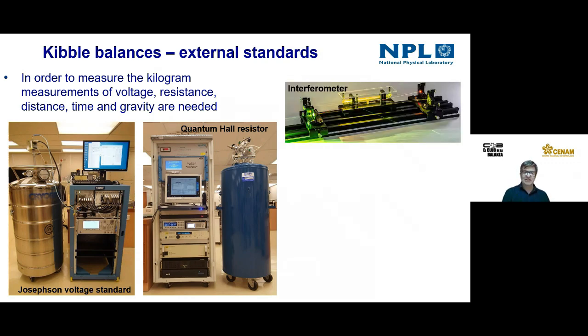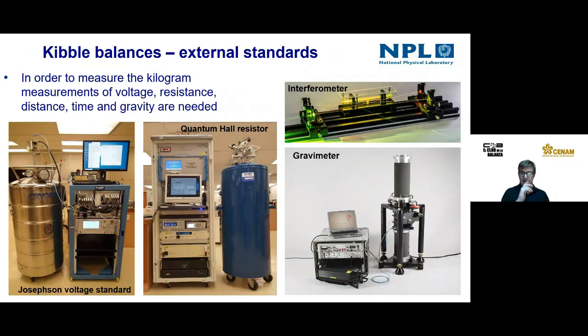The displacement or velocity measurements need to be done with an interferometer. This is not so much of a problem because it's a fairly basic, relatively cheap piece of equipment, but it also complicates the apparatus because you need to find a way of installing it essentially in a mass balance. And you need to measure gravity to convert the forces measured by the kibble balance to masses, which is essentially what we need to generate.